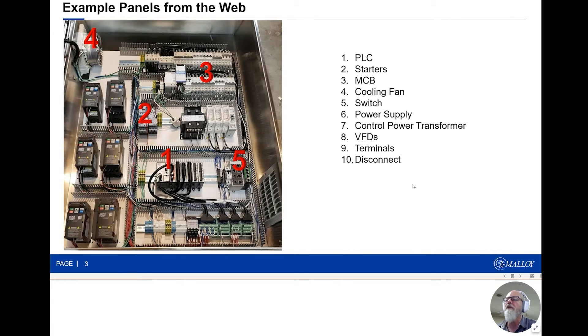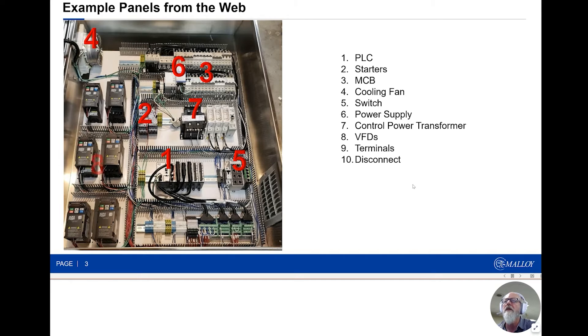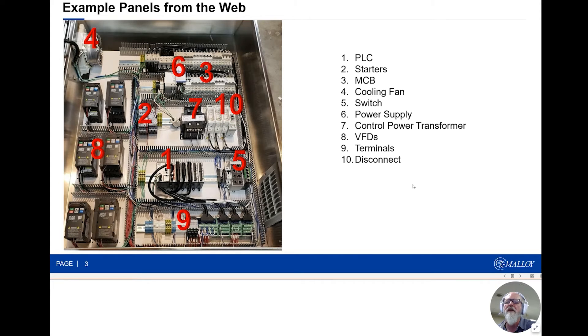The Ethernet switch is present, just like the first example. The power supply, same thing — it takes 120 volts and converts it to 24 volts DC. Then we have a control power transformer, which takes 460 volts single phase and converts it to 120 volts. The VFDs in this case are GS4 Delta or DuraPulse drives from Automation Direct. Then you have terminal blocks and the isolator or disconnect.